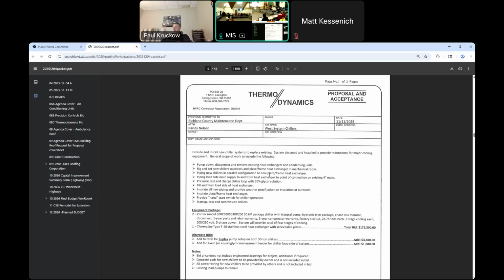A rough number for what it would take to get a redundant pump in there, a new pump? Well, as a for instance, 2 horsepower B&G pumps have gotten crazy expensive like everybody else, but I'm going to estimate a 2 horsepower pump is probably in the neighborhood of $2,500 to $3,500 apiece. The pumps are all 2 horse, but they're slightly different, maybe because of the age when they were purchased or whatever.